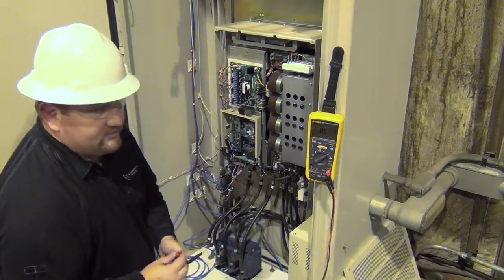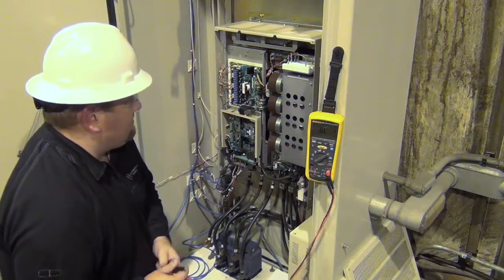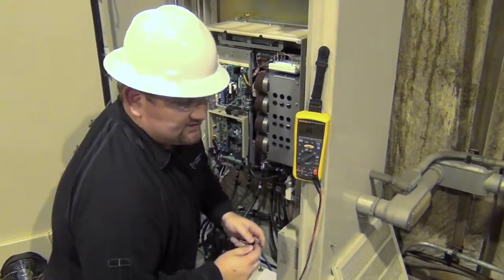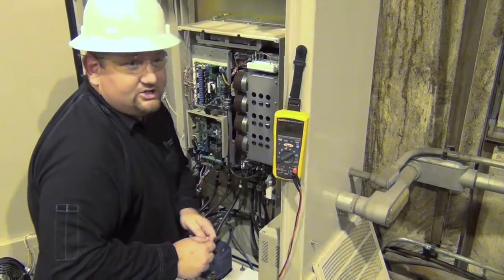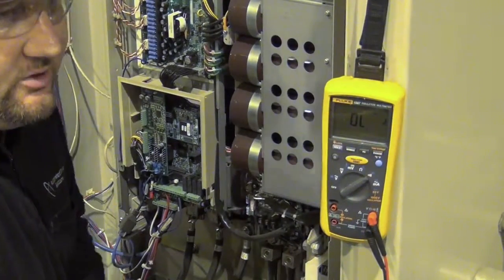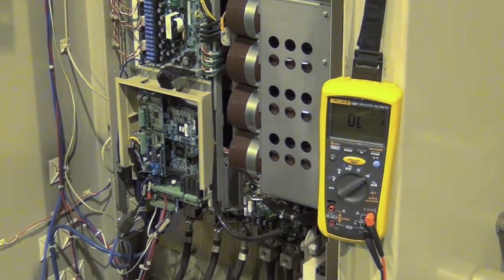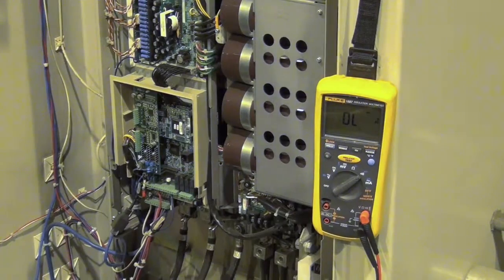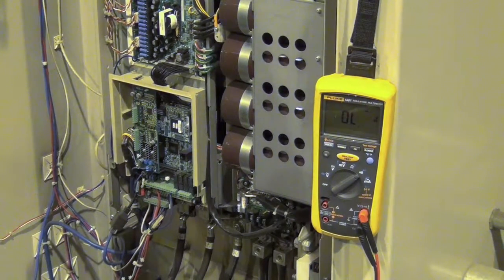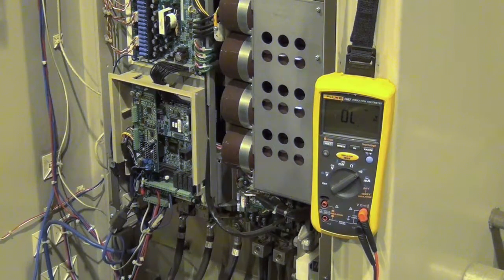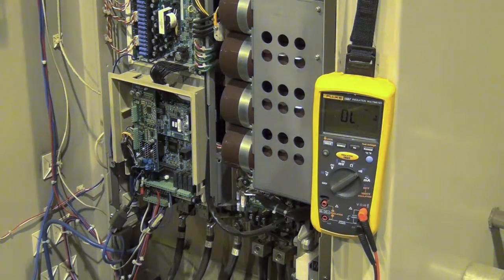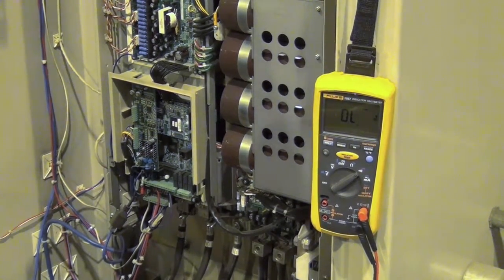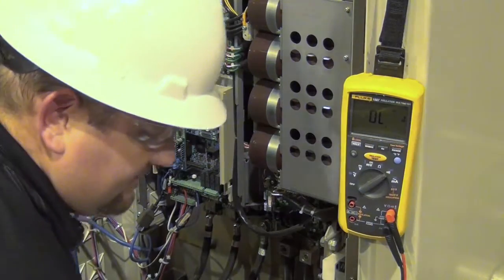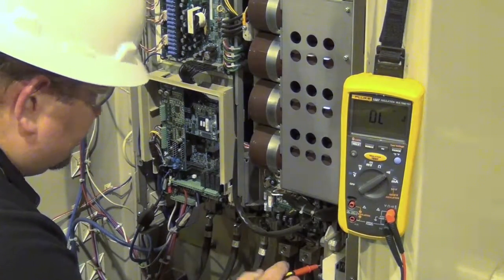So for those of you that aren't familiar with doing a diode test, basically what we're looking for is the meter to pass in one direction, and an ideal diode would give you a value of about 0.4. And then when we reverse the leads on the same connection, we want to see the block. So we want to see an OL reading and that there's no circuit when it tries to pass power the other direction. So I'm going to start with my red lead on the minus terminal of the drive.